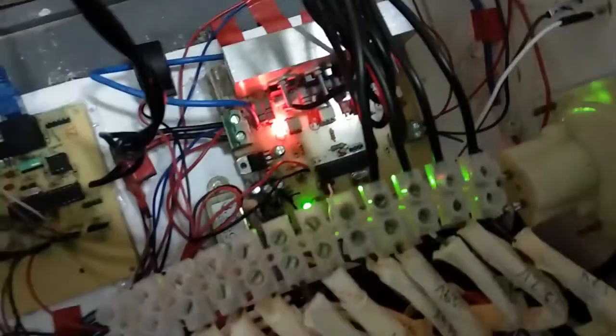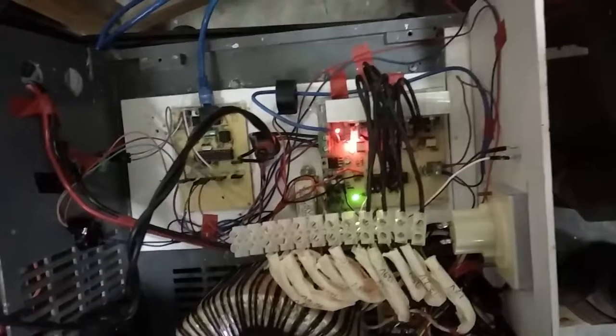As we can see here, there are 4 triacs corresponding to the 4 taps. Now these triacs are working, and in this current meter we can see a fixed constant current of almost 14.5 to 15 amperes, which we are keeping fixed for our project. By changing the taps of the transformer, the AC current taps are adjusted to keep the current fixed. This AC current passes through a rectifier bank with 4 rectifiers in parallel, and once rectified, it passes on to the breaker and charges the battery.